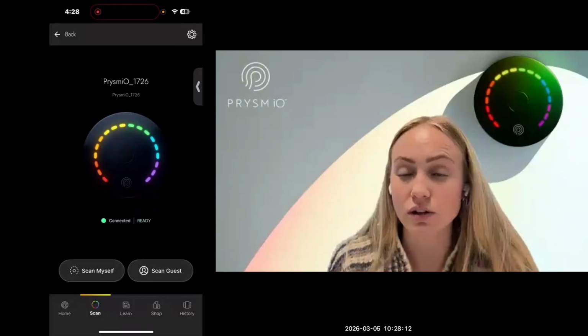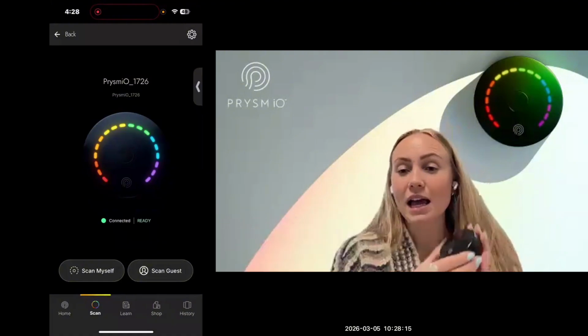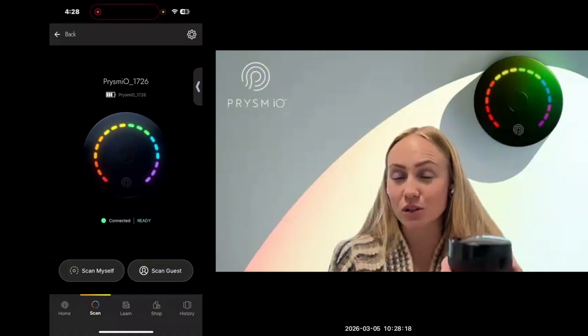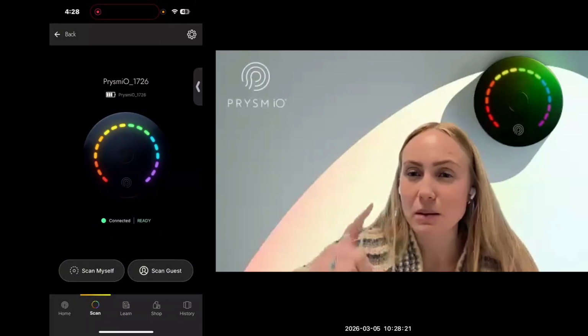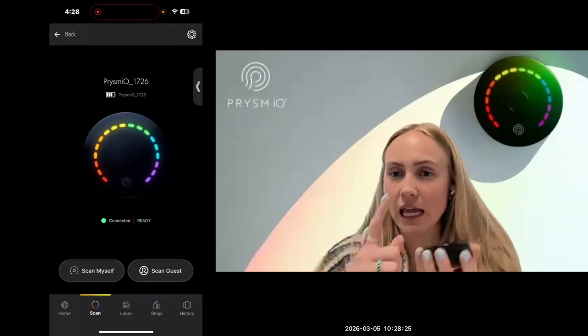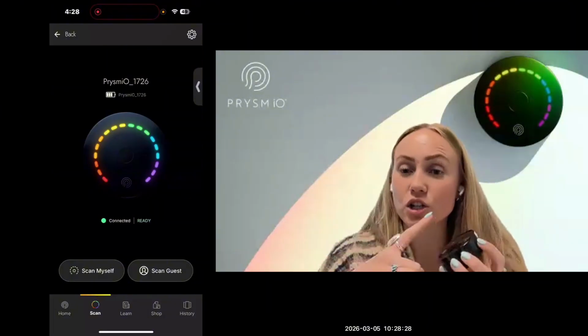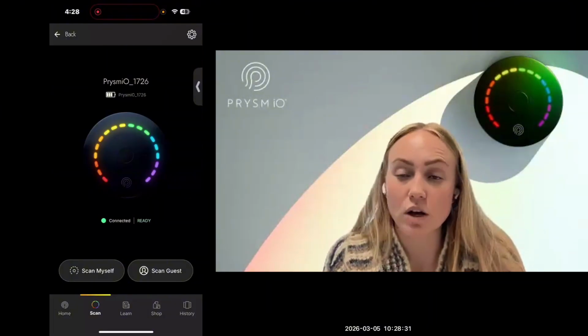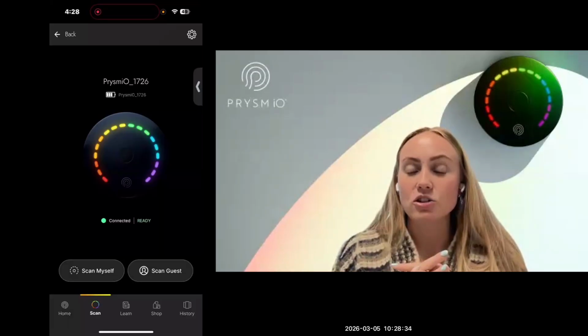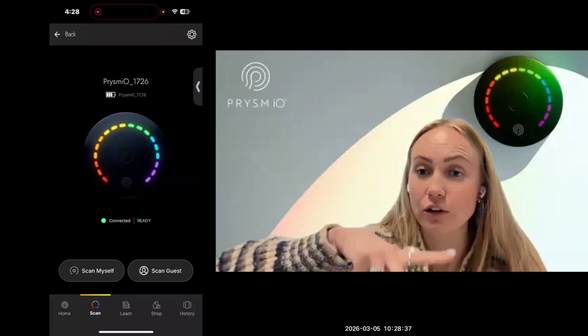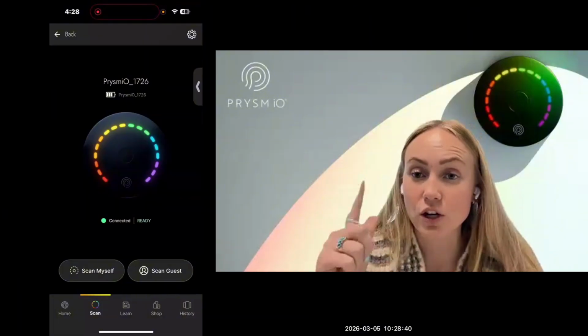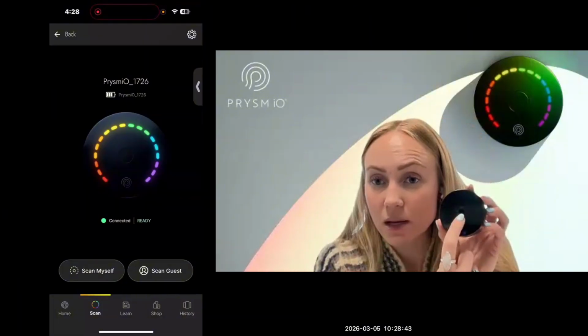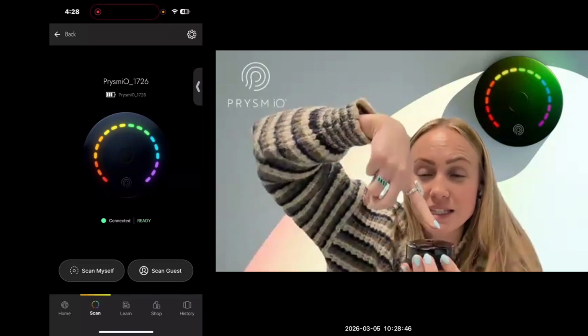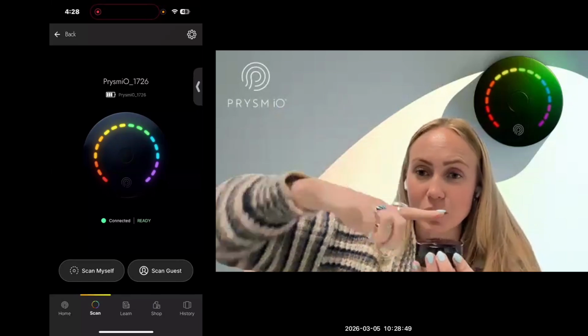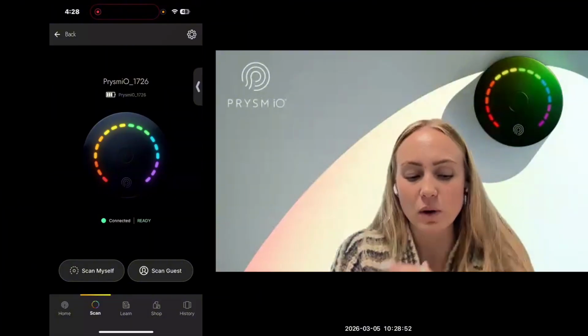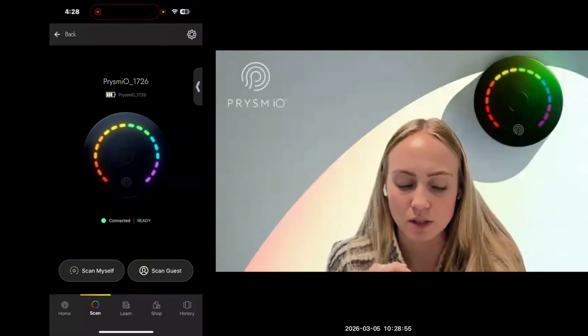The other thing we really encourage is scanning on a flat surface. As fun as it is to hold up the device and showcase it or hold it in your hand, when you do this, you introduce some pressure variability, right? If you're holding it at a certain angle, or if the finger's not on there all the way, that can impact the score as well. So make sure it's on a flat surface, so that the person scanning can maintain their finger pressure. You also want to make sure that the finger's covering the lens completely, so you don't want to be scanning on the tip of your finger. You also don't want people scanning at this angle, right? Because again, that's scanning on the tip. You just want to make sure your finger is flat. That's why it's best to do it on a table, a flat surface. That will help as well.